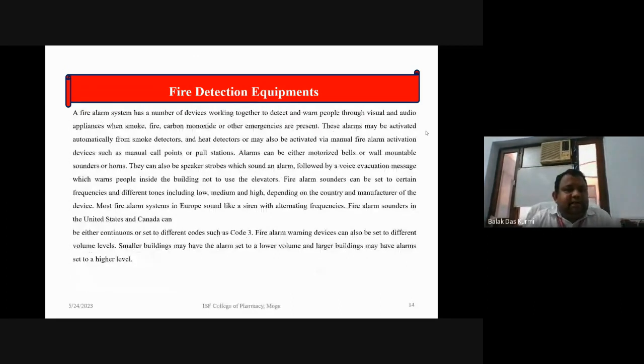Fire detection equipment containing a fire alarm system has a number of devices working together to detect and warn people through visual and audio appliances when smoke, fire, carbon monoxide, or other emergencies are present. These alarms may be activated automatically from smoke detectors and heat detectors, or may also be activated by a manual fire alarm activation device such as manual call points or pull stations.